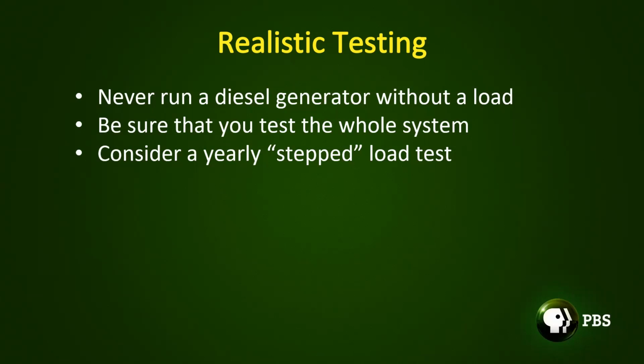And they start at like 25% of rated power. And they run the generator for 12 to 24 hours and make sure it continues to work correctly. And then they step it up to 50% power. Then they step it up to 75% power. And they sometimes, depending on the generator, will take it to 100% rated load. It depends.